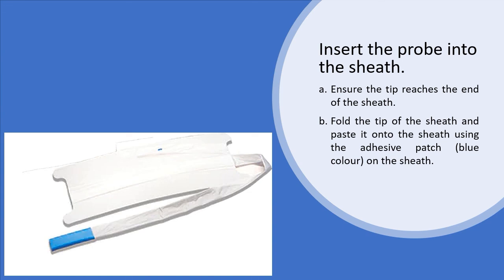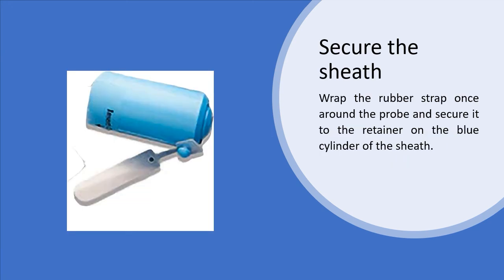Insert the probe into the sheath. Ensure the tip reaches the end of the sheath, and then fold the tip of the sheath and paste it onto the sheath using the adhesive patch on the sheath. This patch is indicated by the blue color. To secure the sheath, wrap the rubber strap once around the probe and secure it into the retainer on the blue cylinder of the sheath.